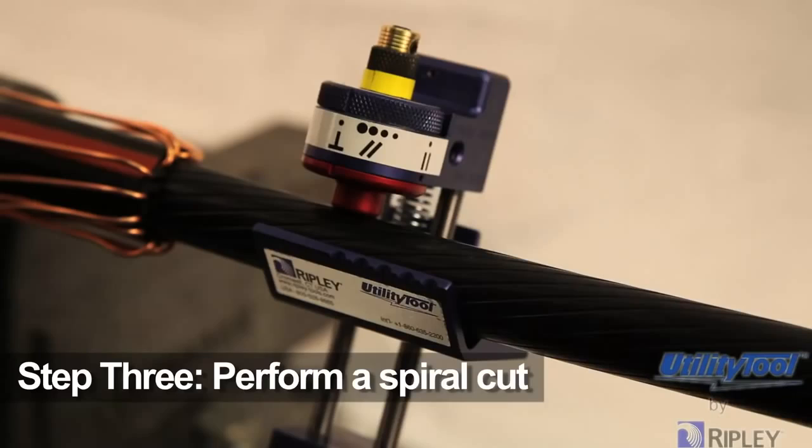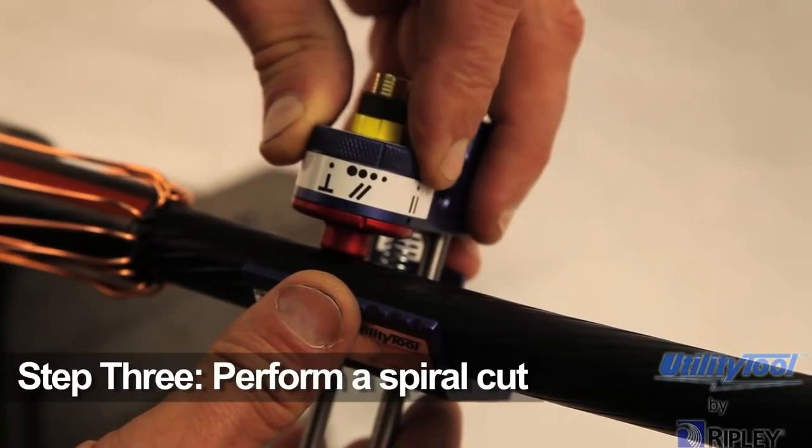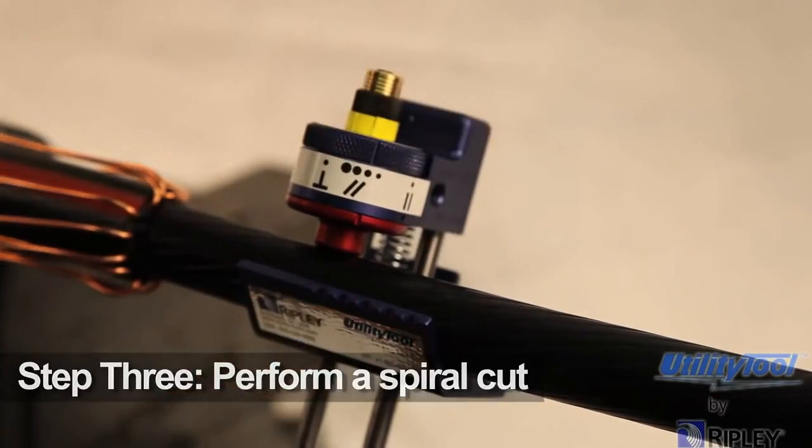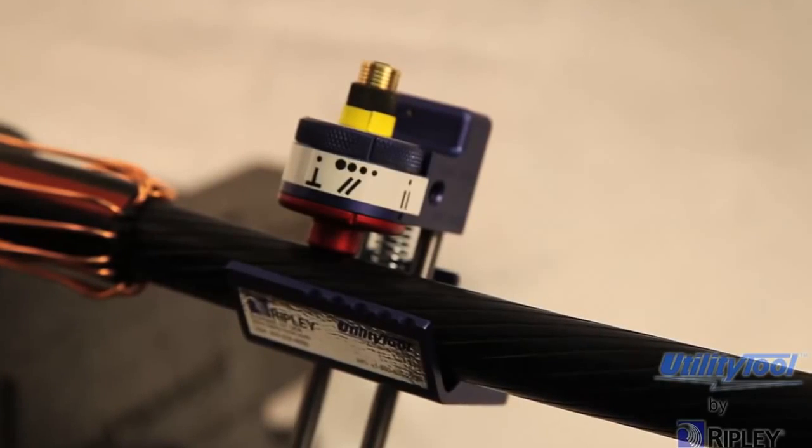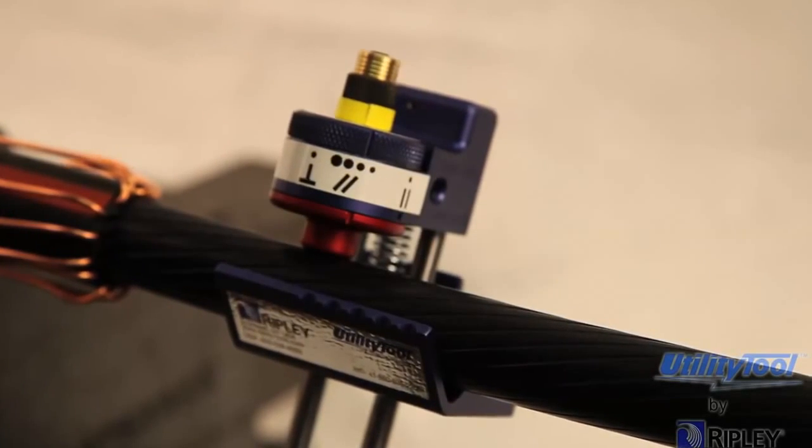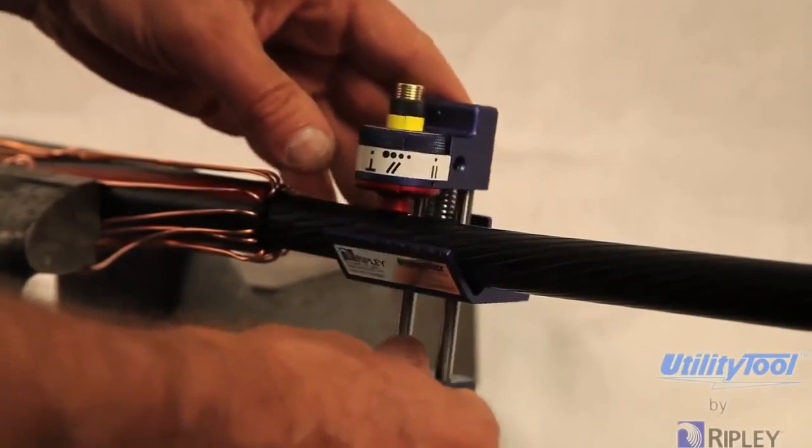Step 3. To perform a spiral cut, first turn the blade positioning indicator to one of the spiral cut locations. The large position will produce the narrowest spiral and it is meant for larger cables. Indexing it further will produce a wider spiral score, typically for smaller cables. Next, turn the tool counterclockwise and allow it to advance toward the end of the cable and completely off the cable.